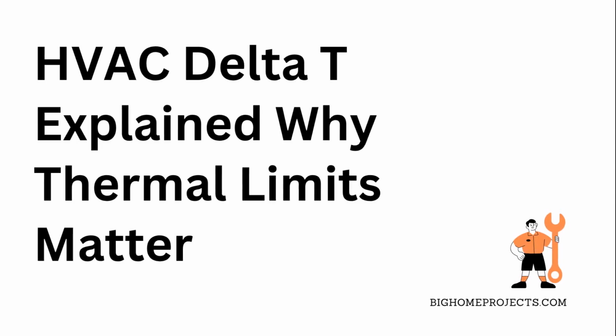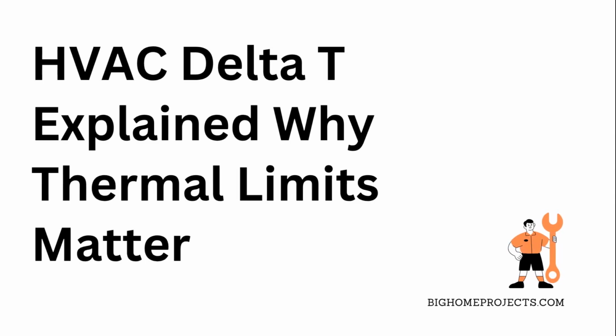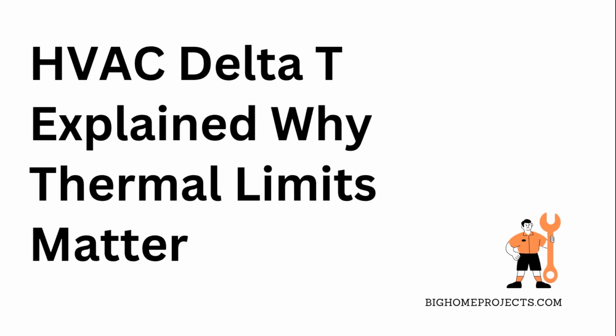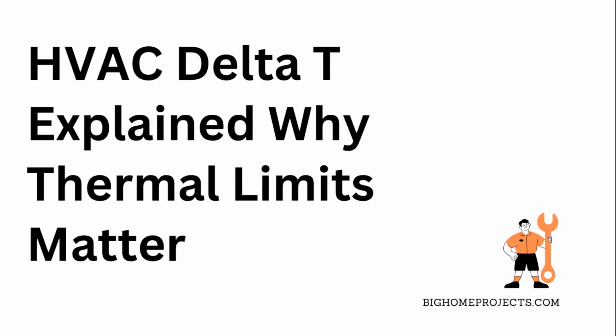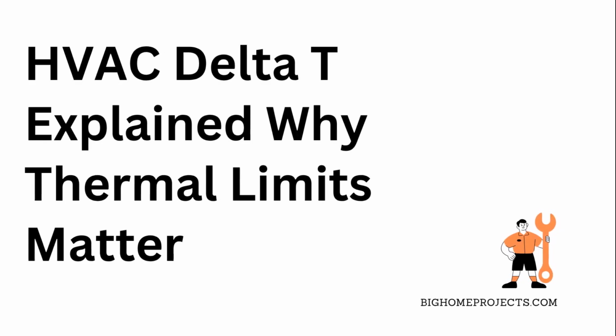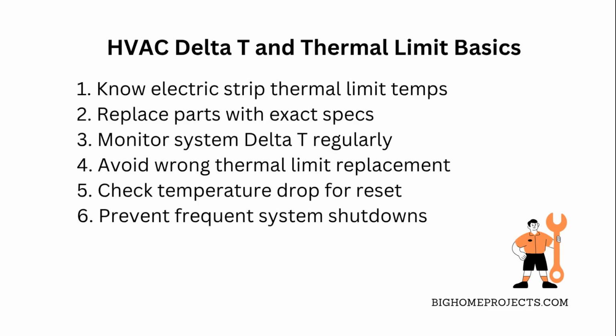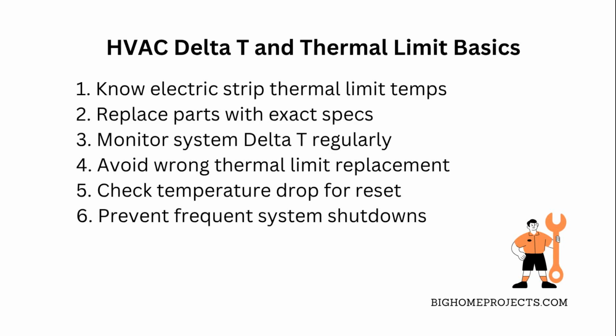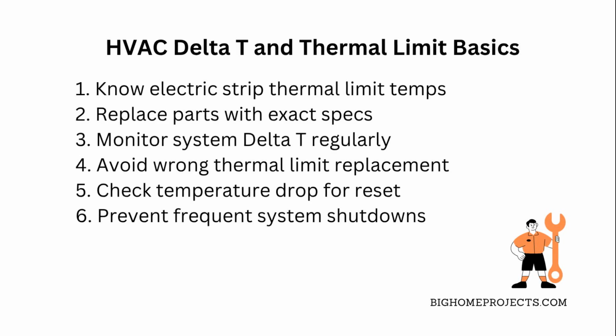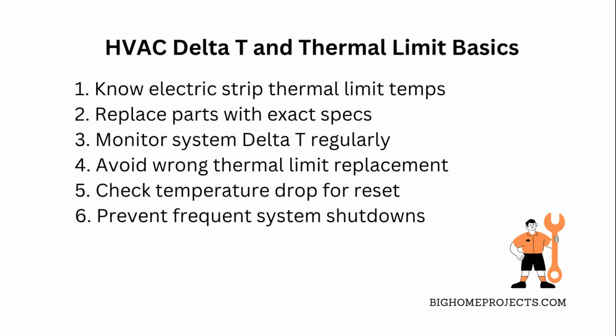Understanding HVAC Delta T and why electric strip thermal limits usually open around 145 degrees Fahrenheit is key to keeping your heating system running smooth. Okay, so when you're working on HVAC systems, knowing that electric strip thermal limits open at about 145 degrees Fahrenheit helps you figure out if the heating element is protecting itself properly from overheating.